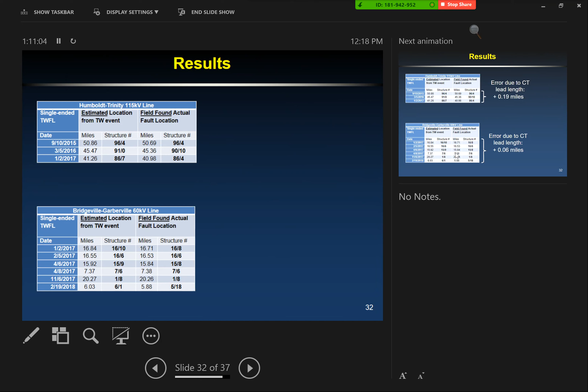Instead of 98%, maybe 98.5%, you're down at 0.6 something—60% of speed of light—because it's insulated CT secondary wire. So if your relay is located at a very big substation where the circuit breaker is almost not even visible off in the distance, that's going to really play into effect.